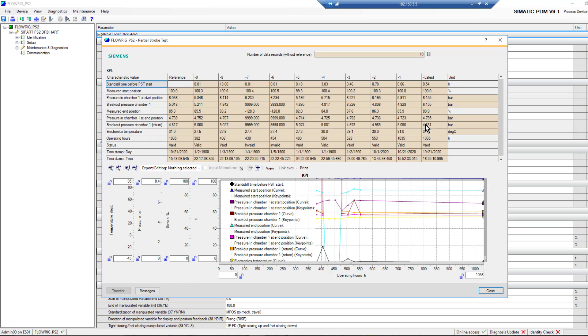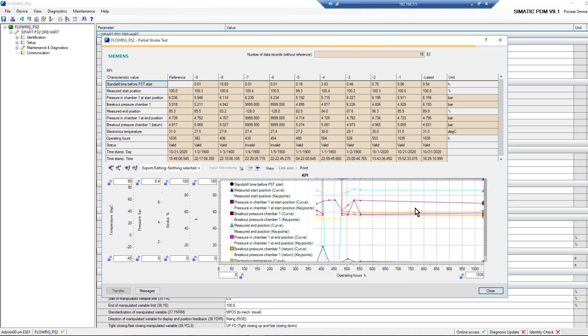Breakout pressures and return pressures to make sure that nothing mechanically is going wrong with the valve. That's proving that something's wrong, and there's more advanced diagnostics in the background to really get to the bottom of what is causing the mechanical asset to fail. There you have it - a look at the partial stroke test, the new KPI dashboards, and really highlighting the power of the new processor with how many curves it's saving on there. I hope you can appreciate that getting this data off to the cloud gives us better traceability over a long period of time on what is happening with your mechanical pneumatic valve positioner on site. Thanks for listening, please share this video with your friends and colleagues. As always, your support is very much appreciated. Keep safe, and I hope to see you soon.